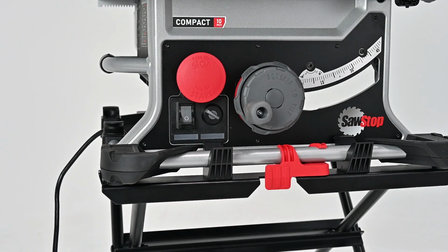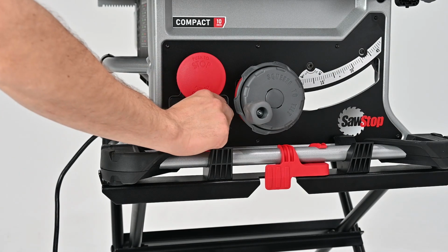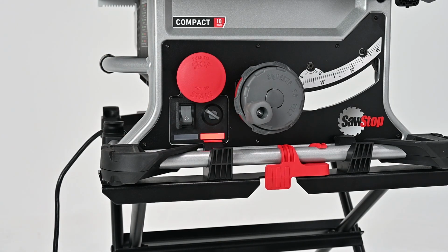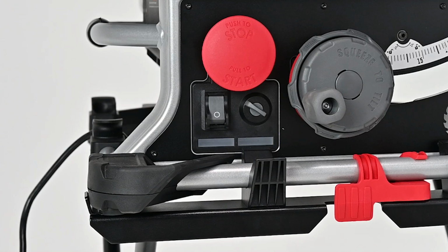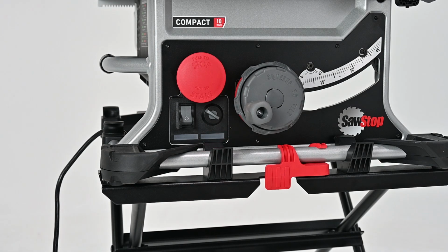The red LED will blink a number of times, indicating the module ID of the error. In this case, 2. The green LED will then blink a number of times, indicating the error ID. In this case, 8. The pattern will then repeat. Here is the cycle again, slowed down. Again, this code represents module ID 2 and error code 8. This particular code means the cartridge key was not in a locked position.